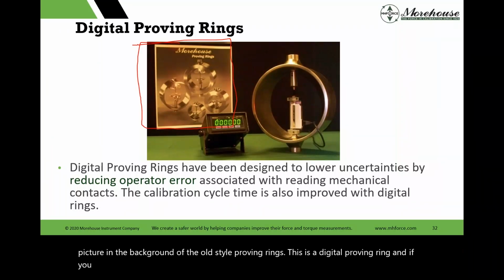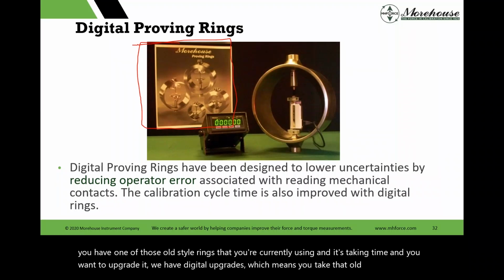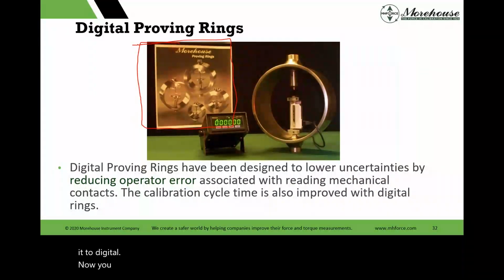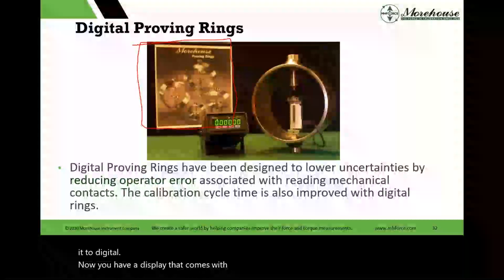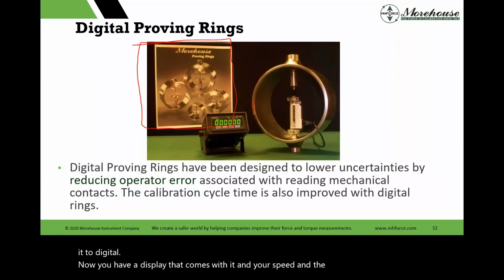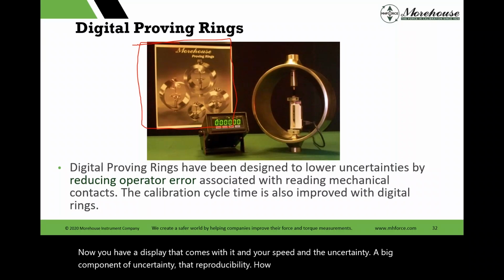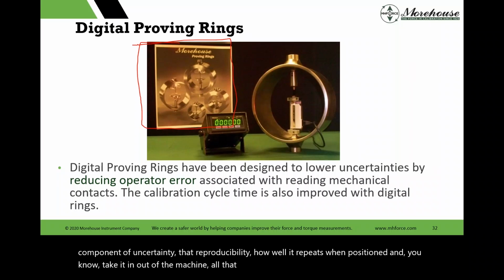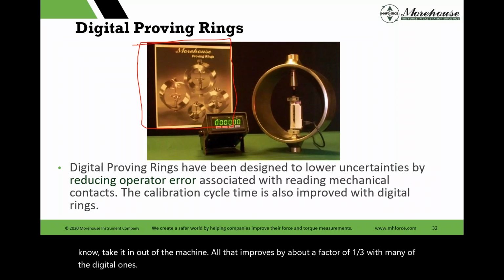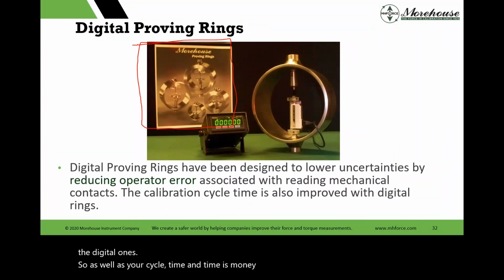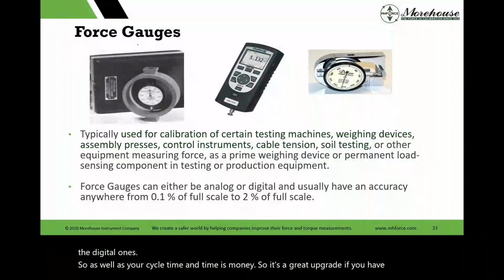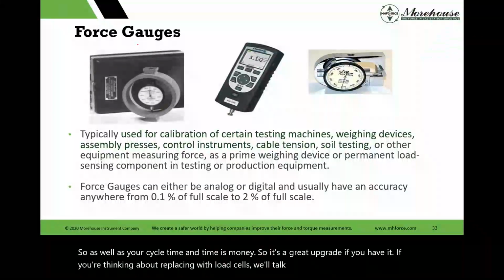And if you have one of those old style rings that you're currently using and it's taking time and you want to upgrade it, we have digital upgrades, which means you take that old ring and we convert it to digital. Now you have a display that comes with it, and your speed and the uncertainty improve. A big component of uncertainty, that reproducibility, how well it repeats when positioned and taken in and out of the machine, all improves by about a factor of a third with many of the digital ones. As well as your cycle time, and time is money. So it's a great upgrade if you have it. If you're thinking about replacing with load cells, we'll talk about load cells later so you can make the right decision.